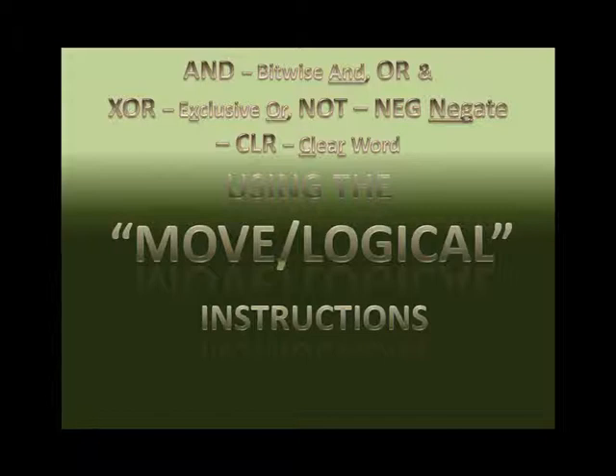The Bitwise And is going to compare two 16-bit words at identical positions, 0 through 15. If they're identical, it puts a 1 in that same position in the destination. So if you're comparing two words and bit 3 of both words are 1, then bit 3 of the destination is going to be 1. If either one is 0 or both are 0, then the destination is 0.